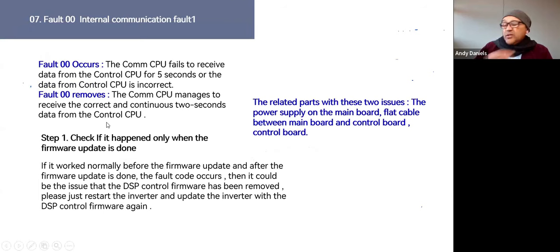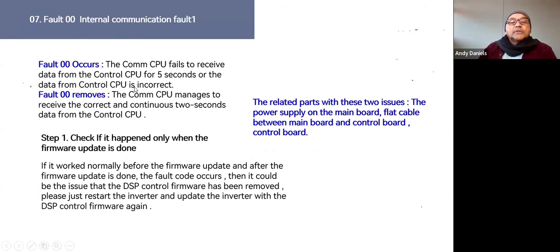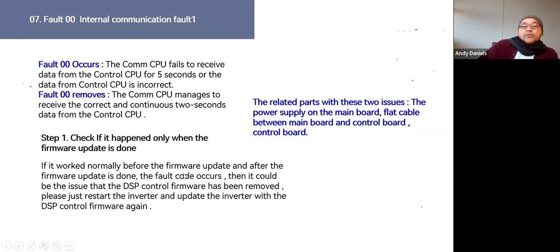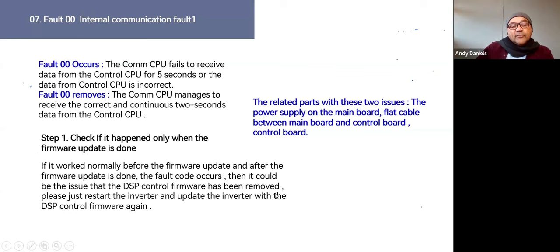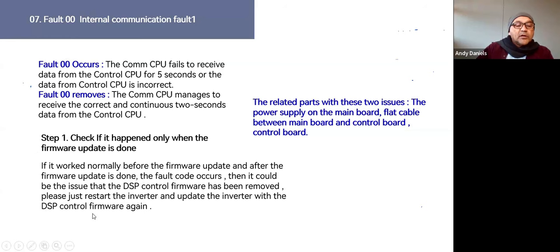Fault 00: the comms CPU fails to receive data from the control CPU for 5 seconds — it clears when data is received continuously for 2 seconds. If this fault only appeared after a firmware update, it could mean the DSP control firmware was erased but never updated. Simply restart the inverter and force-download the DSP control firmware again. That normally fixes the issue.